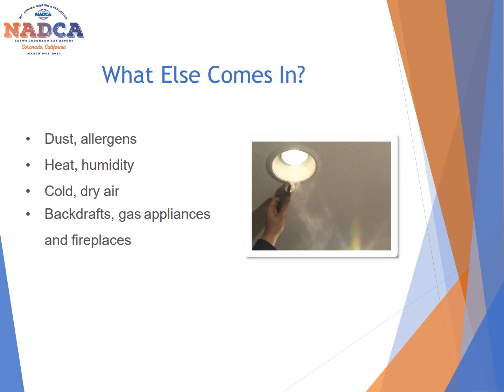What kind of heat and humidity are you pulling in from the attic because you have duct leakage and you've got the building under negative pressure? What kind of cold and dry air would you be pulling in during the winter months, especially from a crawl space or another area that may have all kinds of contaminants in it? One of the biggest issues you can run into is backdrafts and gas appliances and CO2. If the system is not in neutral, it can allow those gases to escape through chimney flues or exhaust flues, and then CO2 or smoke or soot can actually be drawn into the house and create a problem that way as well.